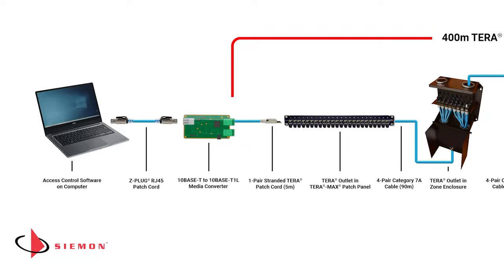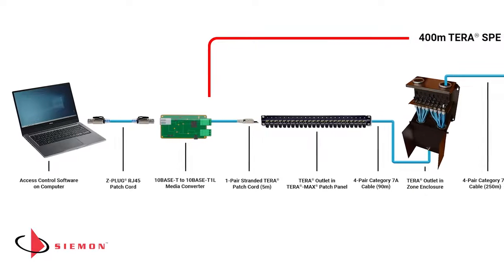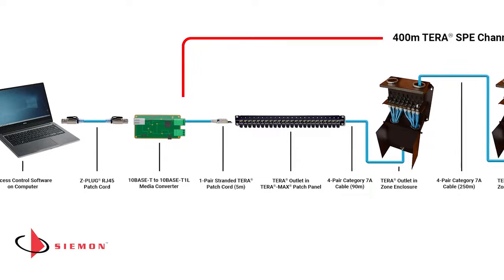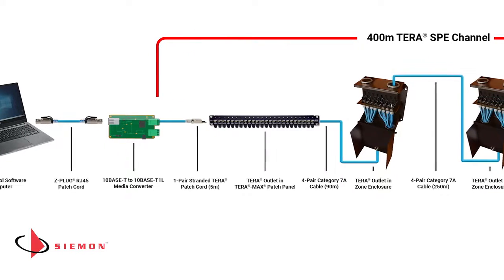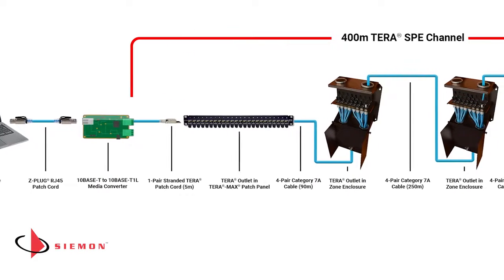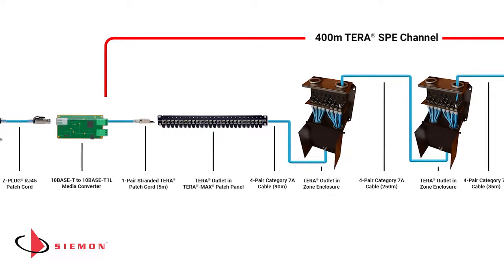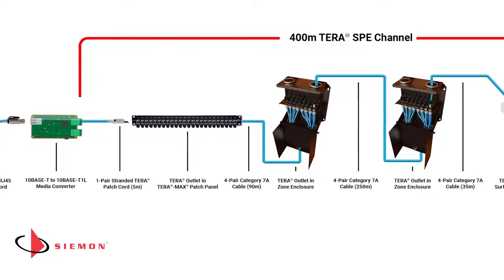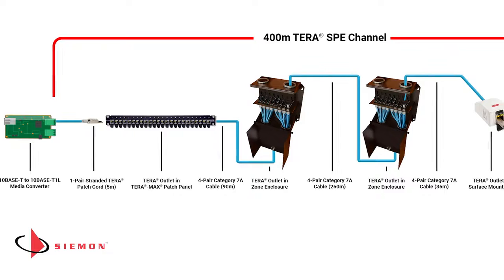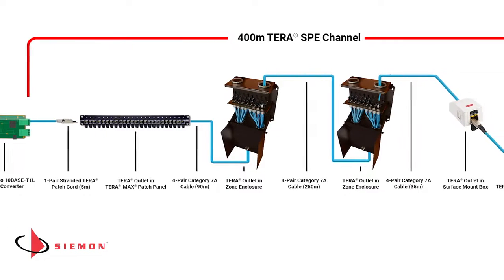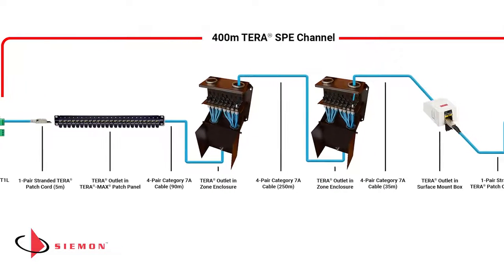Since SPE equipment and devices don't have a market presence yet, our security access control communication must first be converted from TCP/IP at the output of the PC to single pair Ethernet by a media converter. The 10BASE-T1L output signal from the media converter is patched to a TERA outlet with a one-pair TERA cord and then connected with 90 meters of solid cable to a TERA outlet located in a zone enclosure.